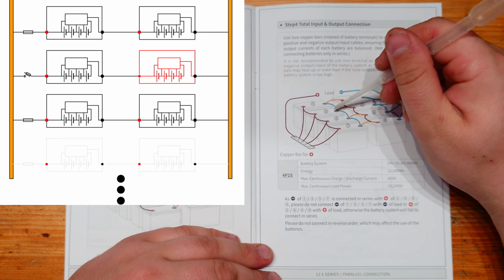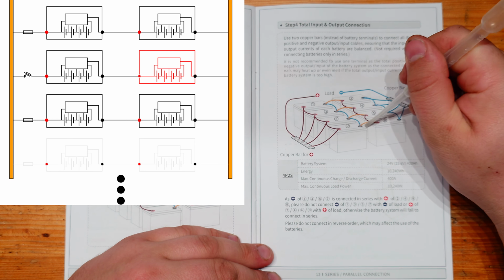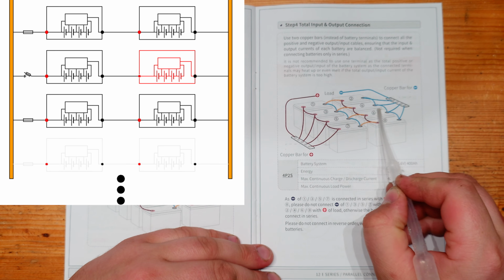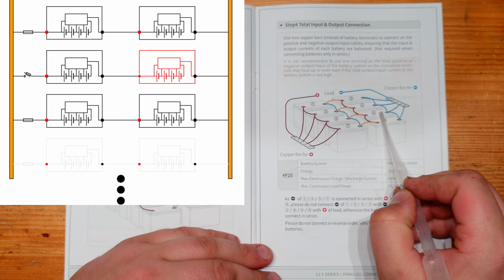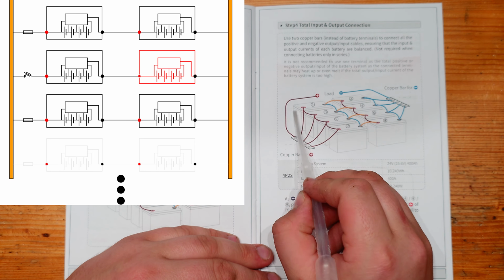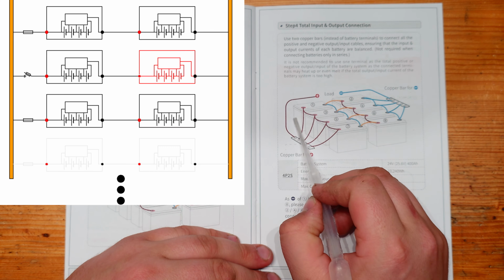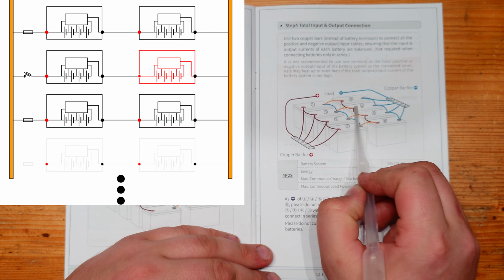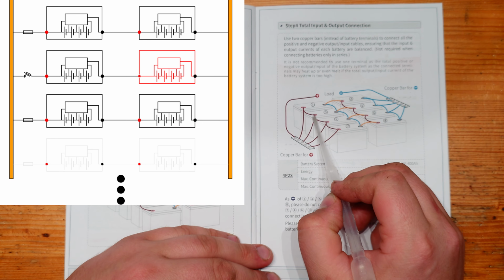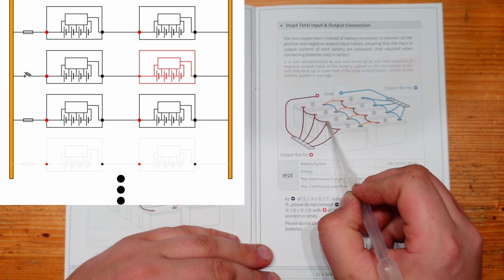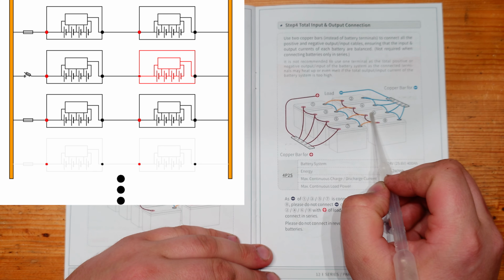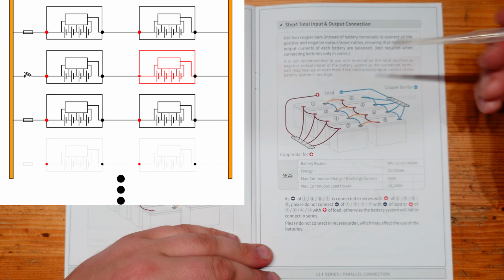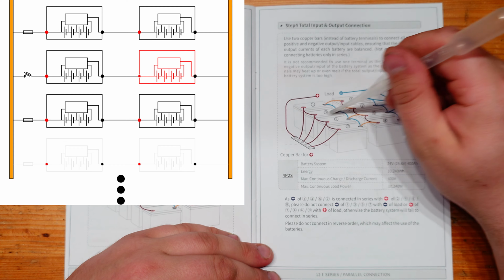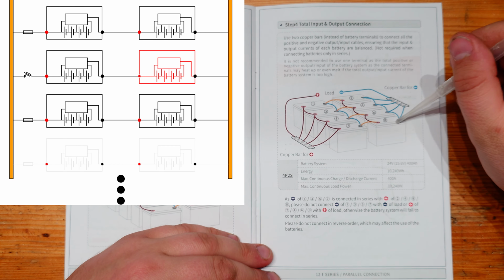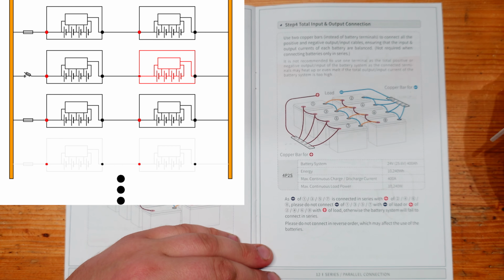Whereas, if you would not use these interconnections, then if battery 6 would die and you would encounter some low capacity of the pack, then all you do is just disconnect the first series, test it, okay, connect it back. Disconnect the second series, test it, okay, it's good. Then connect it back. Disconnect the third series, oh, it's bad. So you leave it disconnected, and then you take care of the bad battery, while the rest of your system, 1, 2, 3, 4, 7, 8, are still operational and your system is still working.